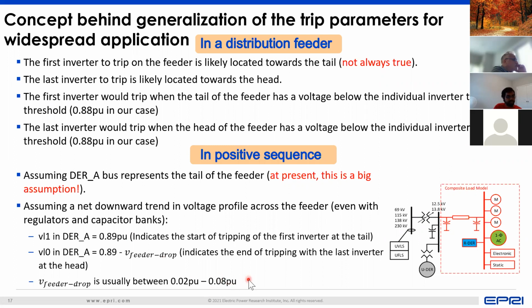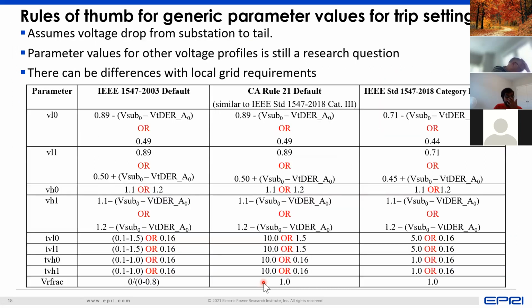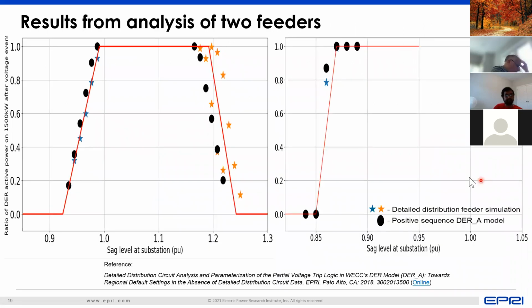But essentially, if we now use this logic of taking into consideration the voltage drop across the feeder, taking into consideration where and when DER would trip, we can get a representation, or we can parameterize these positive sequence aggregated models. And these are just rules of thumb that we derive for parameterizing this model based upon different interconnection standards, whether it's 1547-2003, whether it's California Rule 21, which is similar to 1547-2018 Category 3, or 1547-2018 Category 2. And depending upon which jurisdiction these DER are located in, they can parameterize the model based upon these kind of representations. And if you do that, we can actually start getting a trend of representation of the DER.